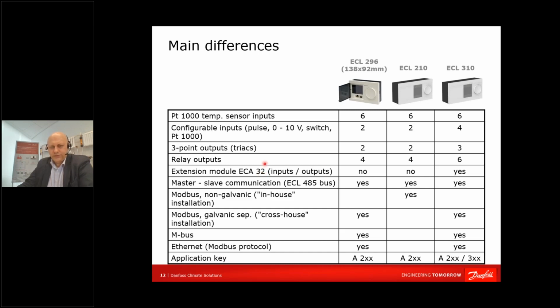Extension module, which is used in some cases to wire a 0 to 10 volt actuator. So that's something new to our applications. I will show it later on. Only ECL 310 can accommodate this module. Master-slave combinations and communications: when you would like to build a larger system, you can connect ECLs together in a chain, and you can have 9 ECLs controlling a big building. So 9 ECLs times 3 outputs, you will get lots of control capabilities.